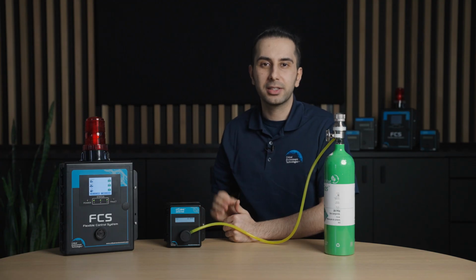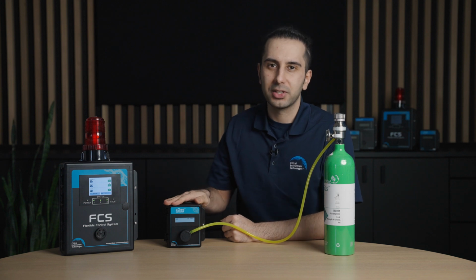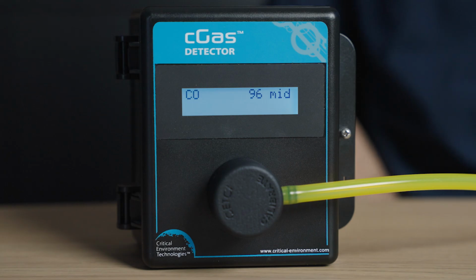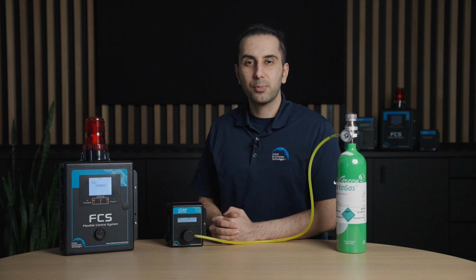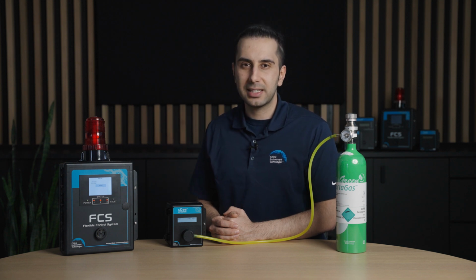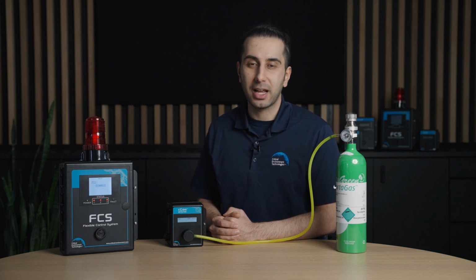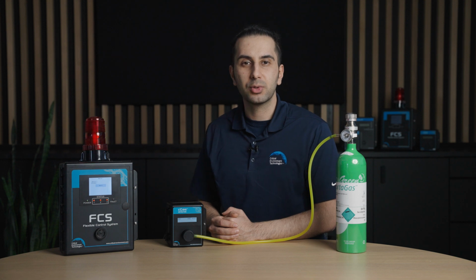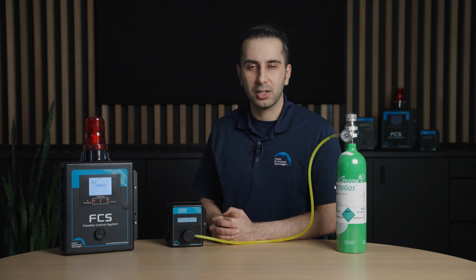Then monitor the detector's display and response actions. Wait for the reading to stabilize and confirm if the reading is correct. Here we see the detector displays approximately 100 ppm, so this is accurate. At this point, the sensor should detect the test gas and the controller should respond as configured, for instance by triggering alarms or activating ventilation.